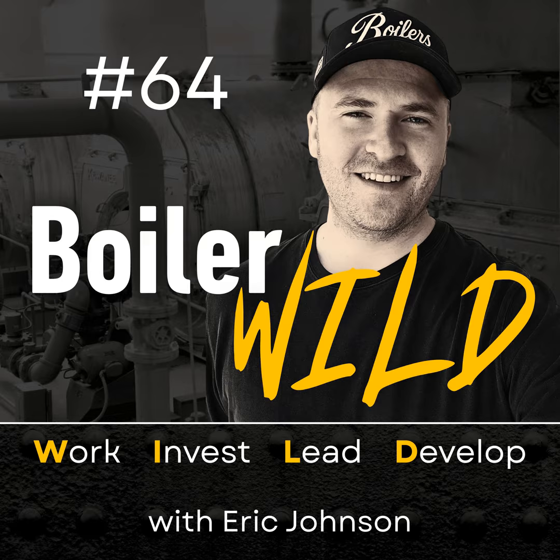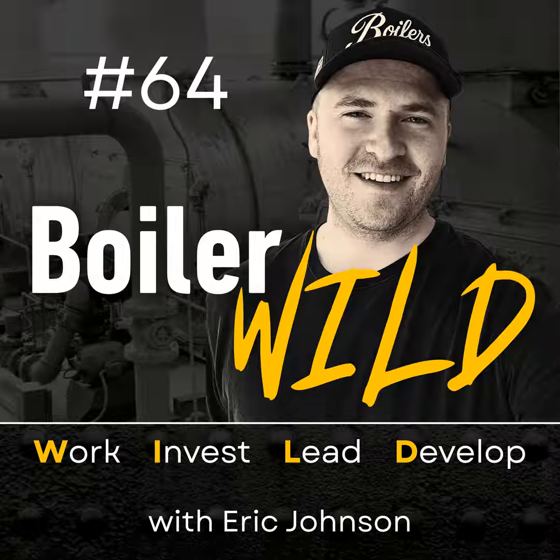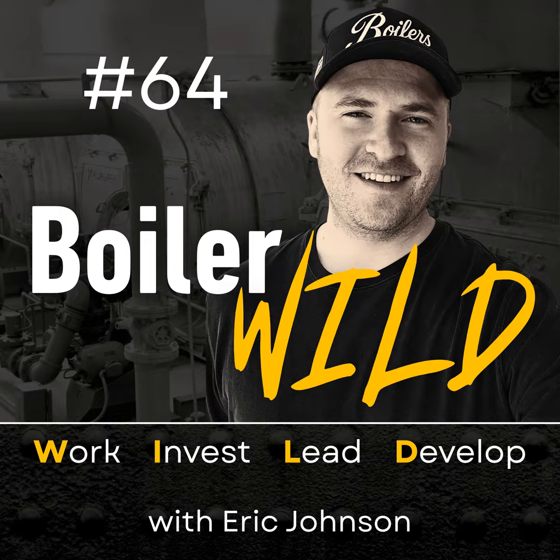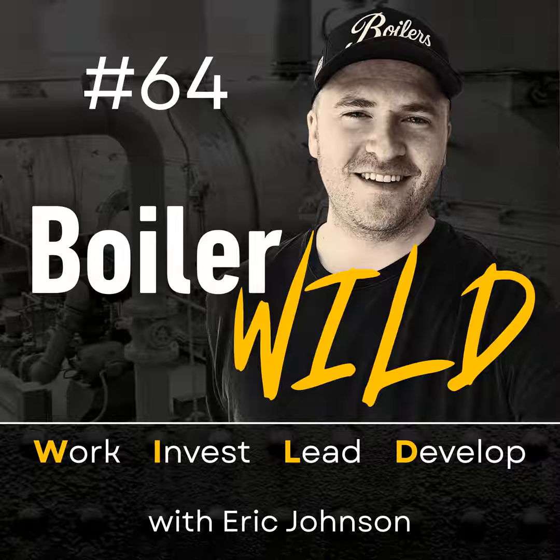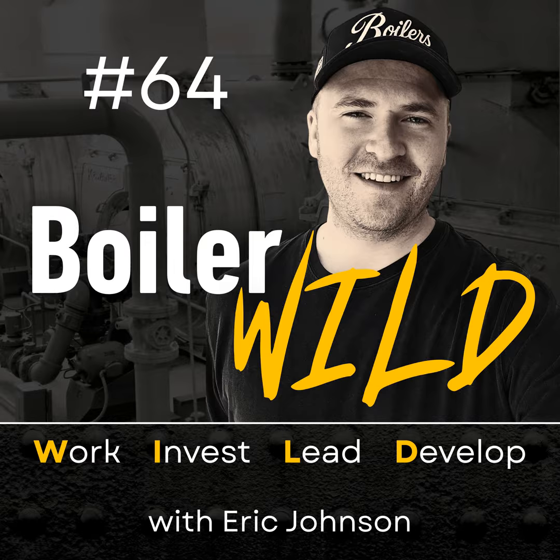Another common scenario that you may come across is on a startup. This can be in any boiler room, but it's very common on startups, in buildings with new equipment where construction is still going on. If all the boilers are not running and they just sit there, the problem is probably not a boiler problem. It is going to be a universal problem. So if the contractor calls you and says, hey, all your boilers aren't running, we came in this morning and all four of them are sitting off, there's no alarms, no nothing, get over here now. Typically you can go through it on the phone with them before you drive over there, because it's always going to be something dumb, especially with a new boiler. And when all of them are off, that is an indicator that something on the outside of the boilers happened.